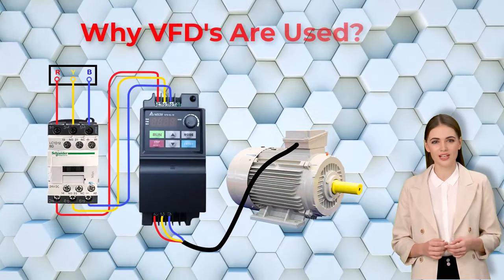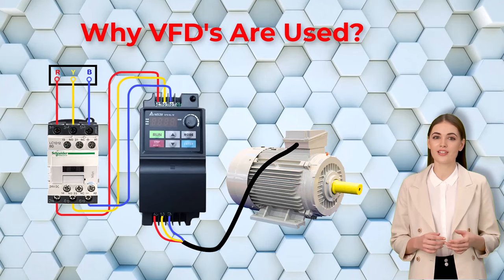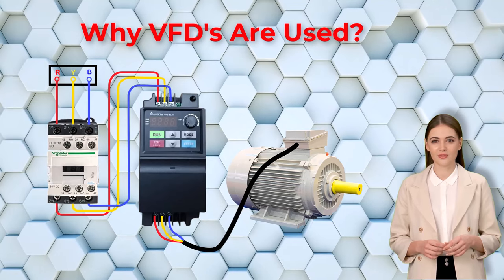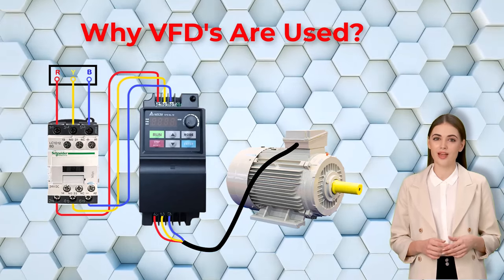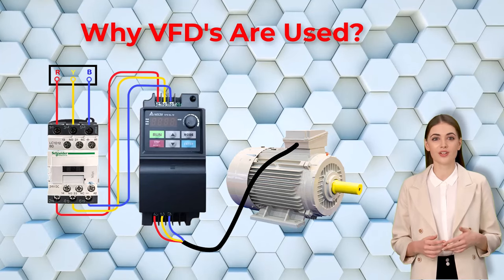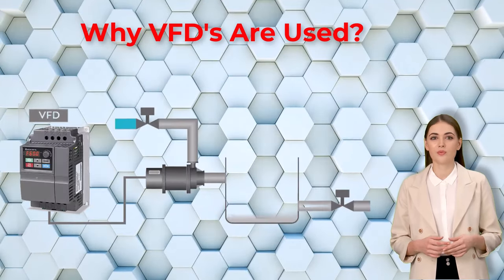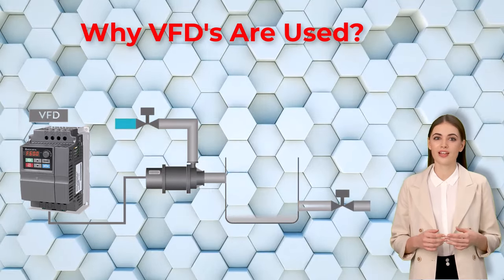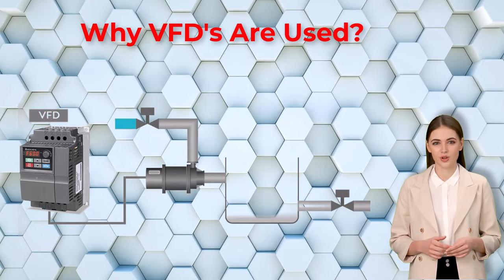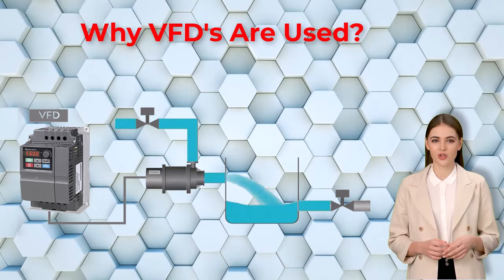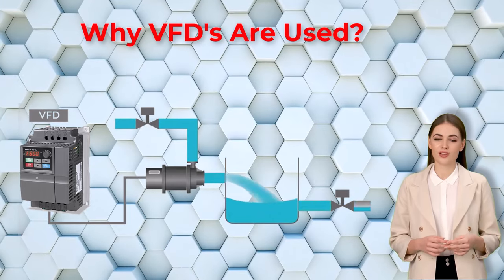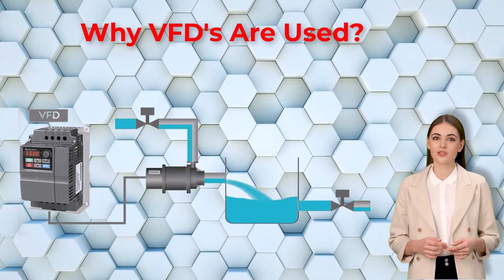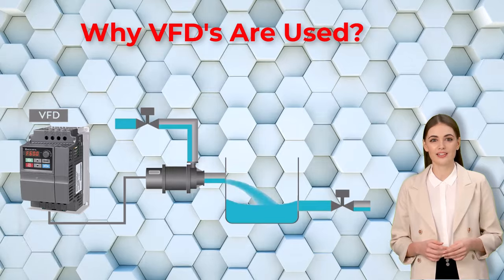VFDs are widely used in various industrial and commercial applications. They can significantly reduce energy consumption by matching the motor's speed to the exact requirements of the application. For instance, in a pump or fan application, a VFD adjusts motor speed to match flow rate requirements, avoiding unnecessary energy consumption when full flow is not needed. VFDs also provide controlled and gentle starting and stopping, minimizing mechanical stress on the motor and connected equipment, extending their lifespan.